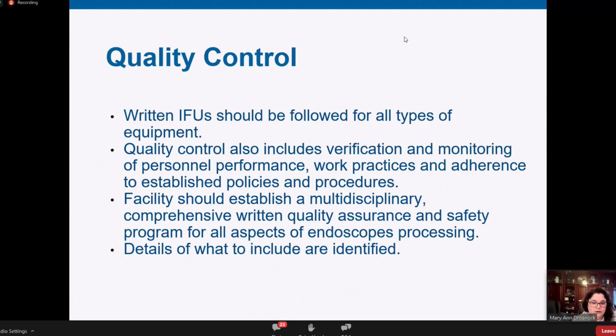We're still doing all of that stuff for our AER, but we're making sure we're doing all the preventative maintenance on it. We're changing filters. We're doing our self-disinfection or waterline disinfections. We're putting things on preventative maintenance. We're testing our leak testers. We may be testing the cleaning process in our AER itself.